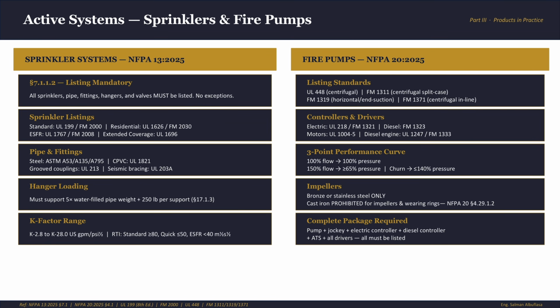Starting with the sprinkler system, or the sprinkler heads, according to NFPA 13. NFPA 13 states clearly that everything essential to a system operation must be listed: sprinklers, pipe, fittings, valves, whatever the standard says, no exemption unless it says so. Listing is product type specific. A sprinkler head is not just any sprinkler head. An ESFR, a quick response, a residential sprinkler, a standard, they've all been tested and listed for the specific type of hazard based on their fuel loads. Their K factors are not the same, their RTI index is not the same, all designed specifically for their fuel loads. We cannot substitute one for the other. We cannot assume that one head fits all. That's it. As simple as that.